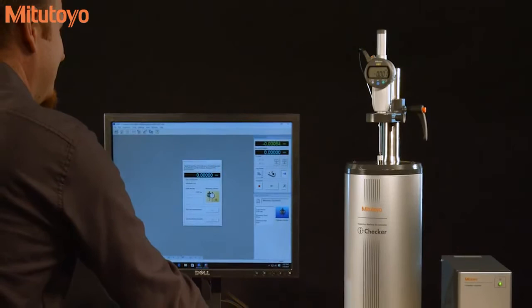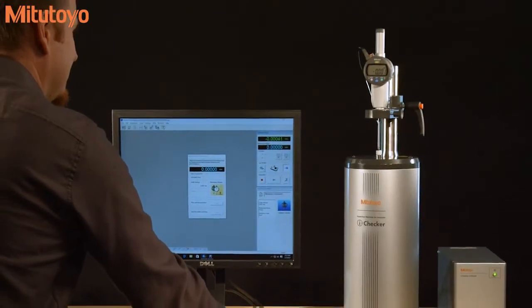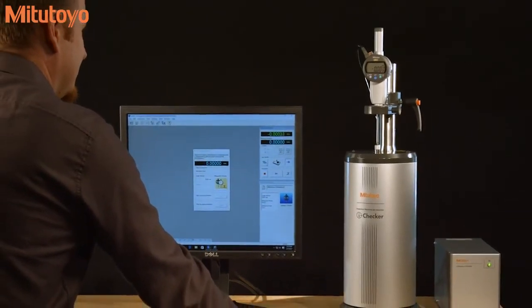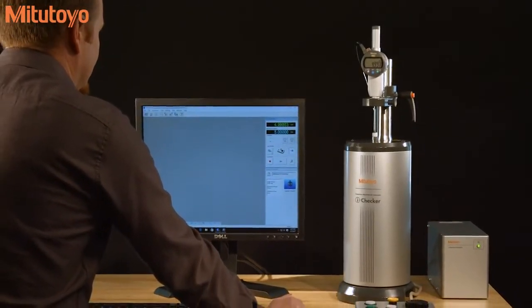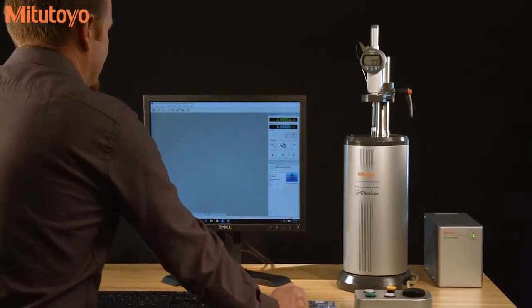Electronic gauges that have data output capability can utilize the i-Checker's full auto mode, enabling fast and efficient calibration.